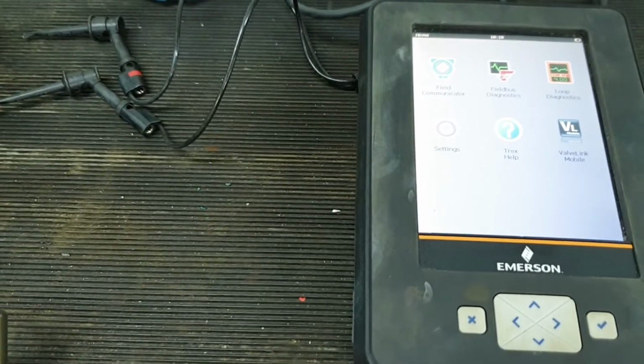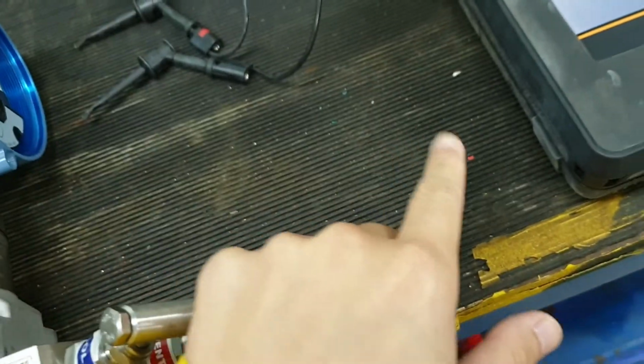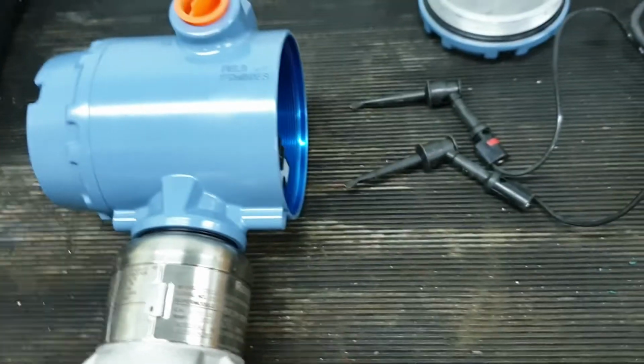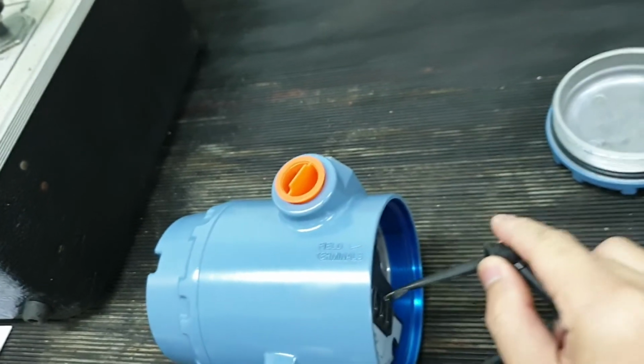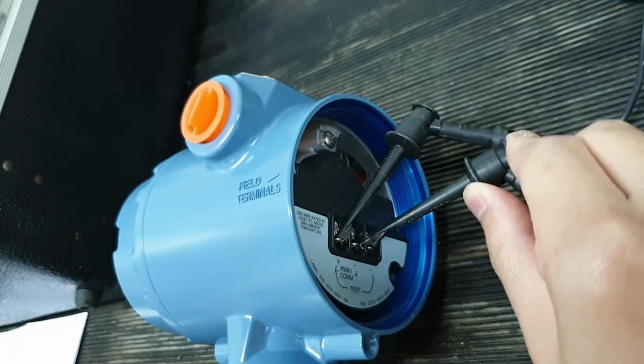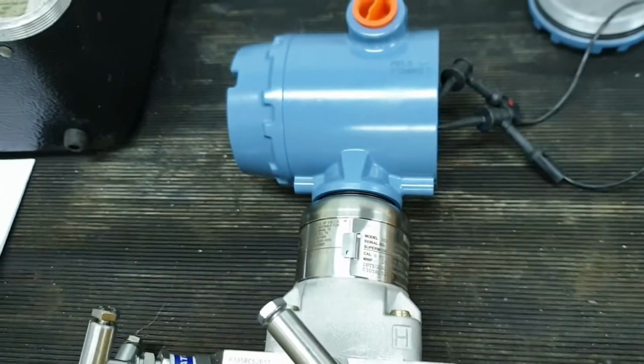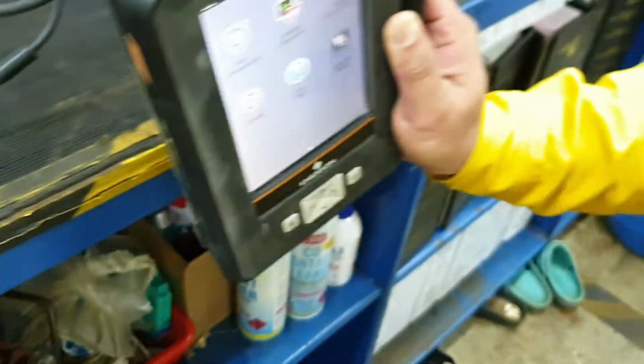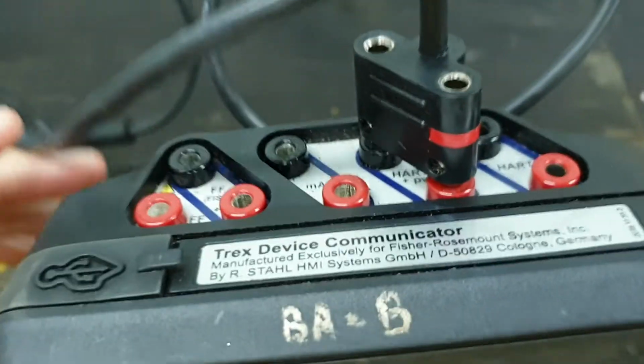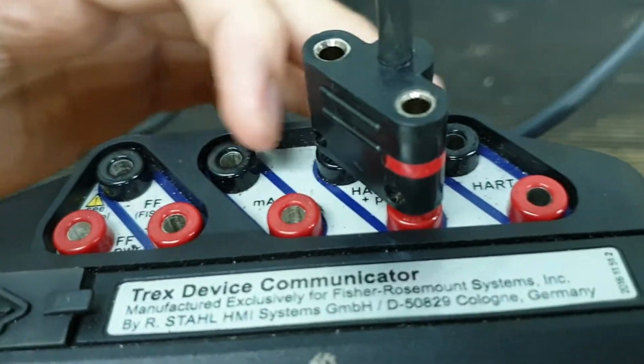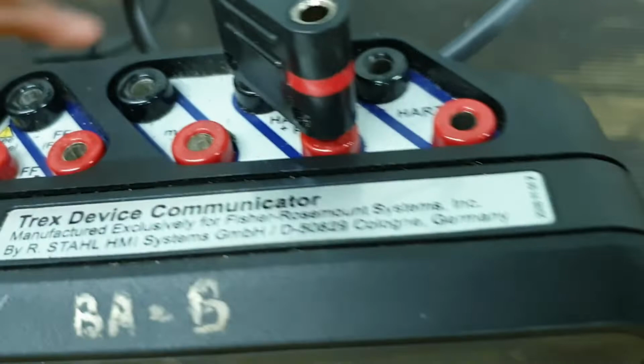So firstly, we are going to connect our communicator to our transmitter. The red probe will be connected to the plus side, and the negative probe will be connected to the negative side. Since this transmitter is not powered by any side equipment, we're going to use this device to power up our transmitter. As you can see, the transmitter has three probe connections at this side. For testing, we're either going to use the HART type or the HART plus power. Due to the reason that we don't have any power here, we will select this point for testing and calibration.